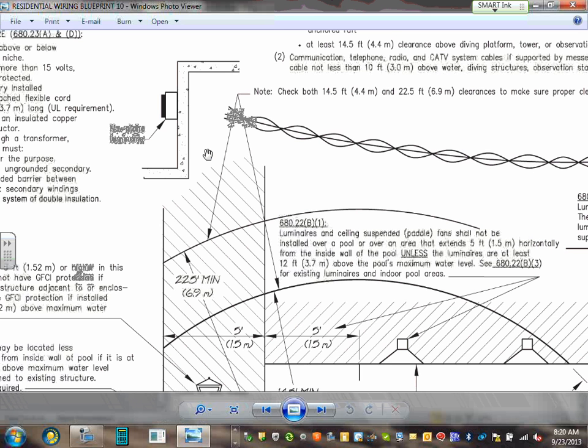Now, reflecting on what we're doing right now for the project that you guys are doing, a quick reminder: you need one receptacle not closer than 6 feet, GFCI. The pump also needs to be on a GFCI circuit breaker, 2-pole. You have a heater that you're going to be wiring. That heater will be located around the swimming pool. We're going to have lights. Your lights are going to be further than 5 feet away from the swimming pool. And we're going to have a switch for the swimming pool light.